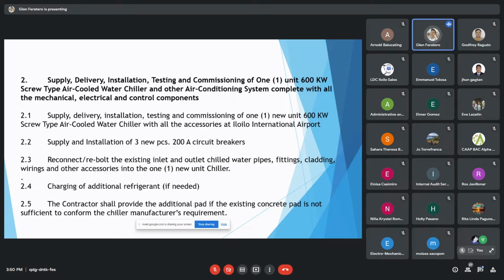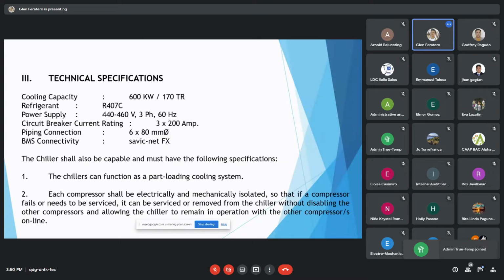Reconnect and rebolt the existing inlet and outlet chilled water pipes, fittings, cladding, wirings, and other accessories into the new unit chiller. Charge additional refrigerant if needed. The contractor shall provide an additional pad if the existing concrete pad is not sufficient to conform to the chiller manufacturer's requirement.